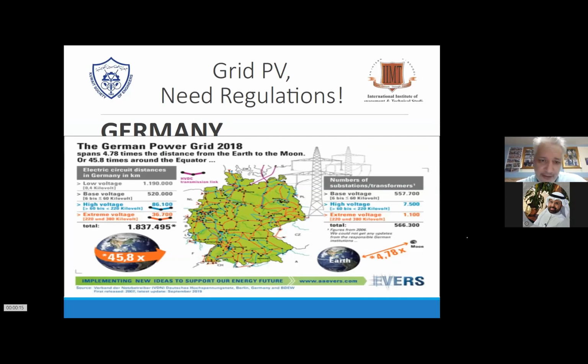So that's why sometimes, when you, for example, study in Germany and they give you these different programs, PVGIS or PVsyst, and you go then to other countries and try to copy those installations. I mean, the European climate, first of all, especially in Germany, is very cloudy. So there's like 1,000 to 1,200 kilowatt hours per kilowatt peak installed. So a 10 kilowatt system can give you between 10 and 12,000 kilowatt hours a year if it's only feed-in. Now more popular are these hybrid systems where you actually charge batteries and use it also for self-consumption. But you should know roughly what a system like that can give you in the long run.